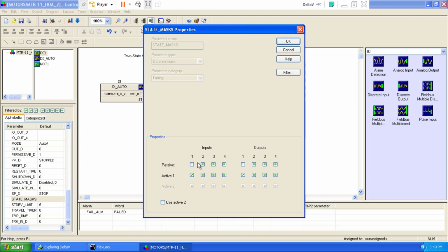This is just like saying a normally closed or normally open. You know, in a normal state, if it is an NC switch, then it is closed. If it is an NO switch, then it is open, right? In a normal state. So whenever you energize it, you tell it use energy, or you want to take it into an action state, the pump or the motor here starts running, and then I receive a feedback of running.